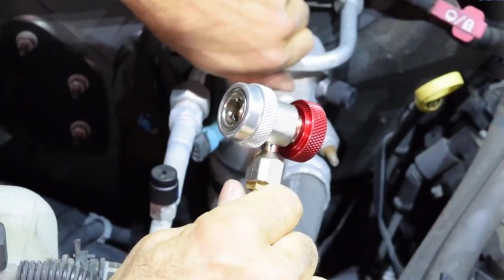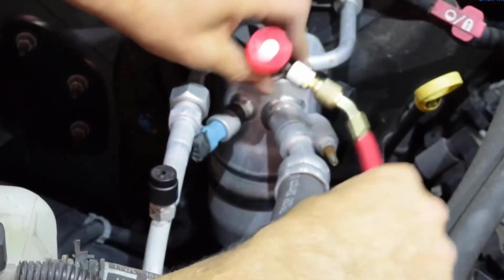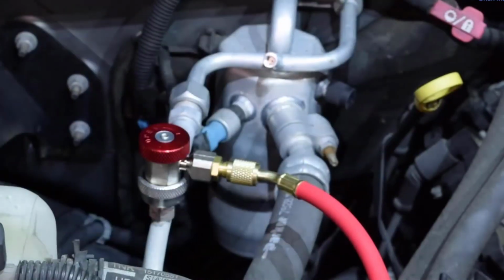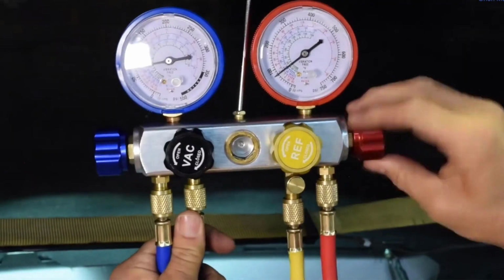The durability is its strong point. Hoses are also made of thick material, and they last longer. But it has some issues with the replacement adjustable connectors. The gauge is accurate. It uses a sight glass in the manifold, which helps to view the flow of the refrigerant. The quick connect hoses are good, but there are instances where they leaked. So, take care of them properly.